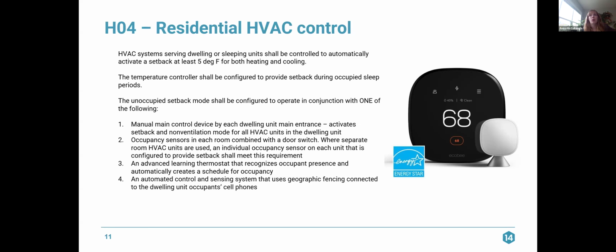And then the unoccupied setback mode has to be configured to operate in conjunction with one of the following. You do not have to comply with all 4 of these. And I really tried to simplify them. There's additional information available in the code around each of these. I'm happy to answer any questions you have. The first is like a master switch at the dwelling unit main entrance. It's like you walk into a hotel room and it has a master switch. It activates the setback and non-ventilation mode for all HVAC units in the dwelling unit. So you turn the switch off, you're leaving, it's going to set back your HVAC.